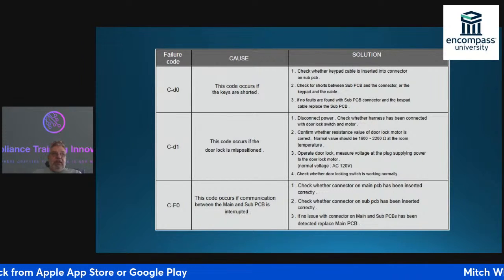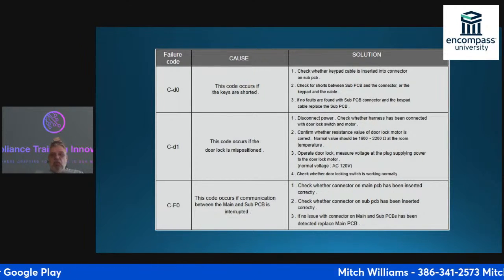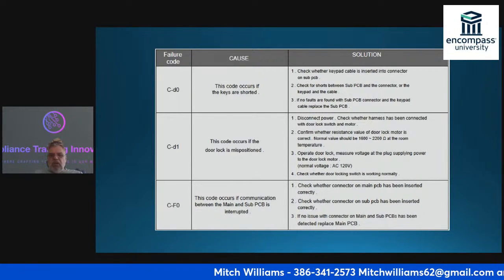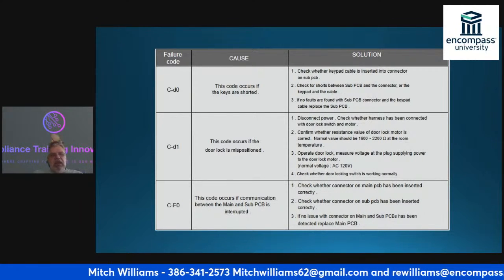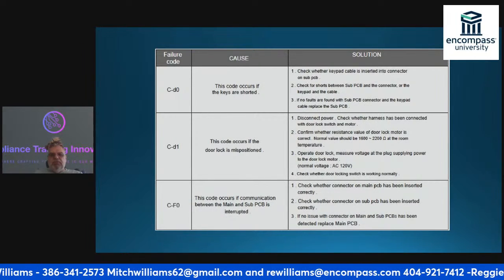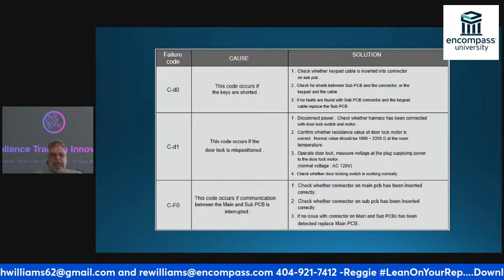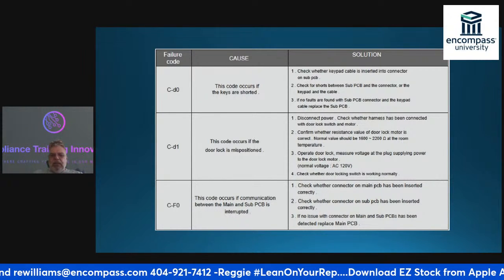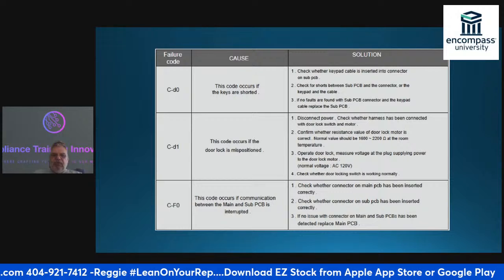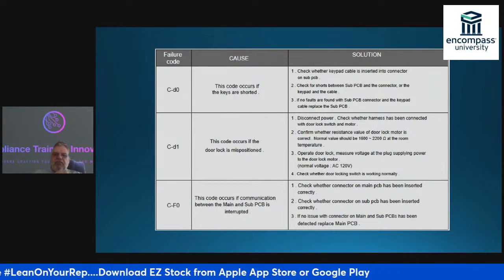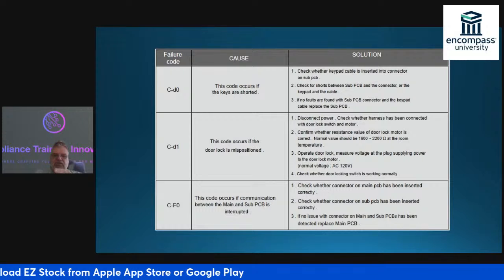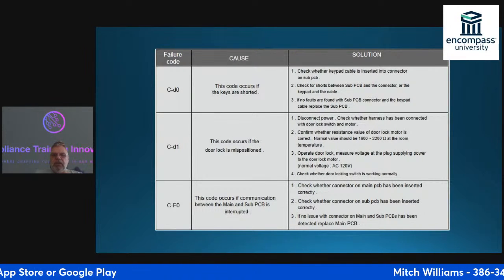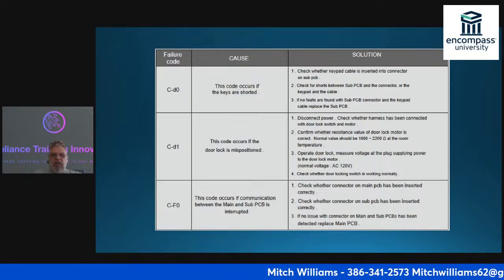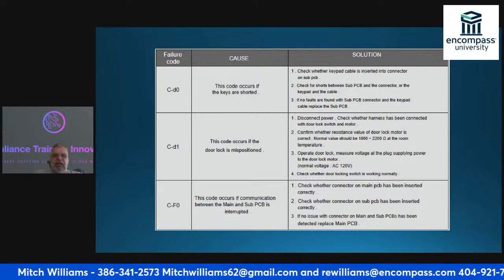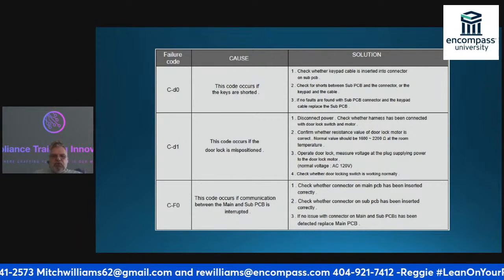One of the things that you will find a lot of times is that I can realign the door locking mechanism itself, and I can get it to work properly. Before I go and try to replace everything, if I see that it's actually working when I try to pull it in, that tells me that my C-D1 error code is not right. All I got to do is realign the switch.